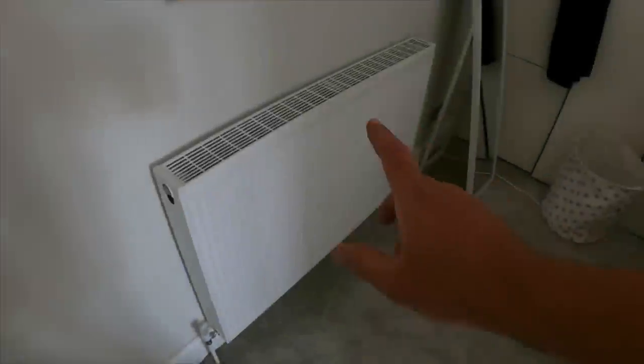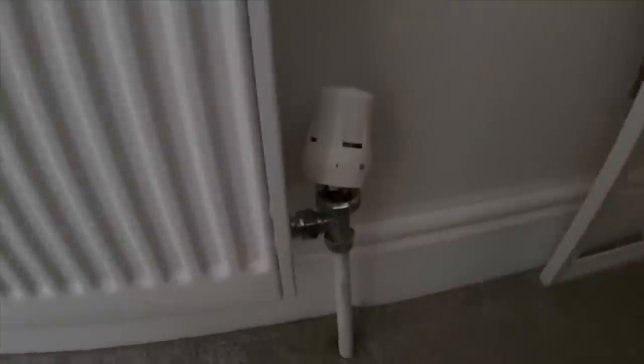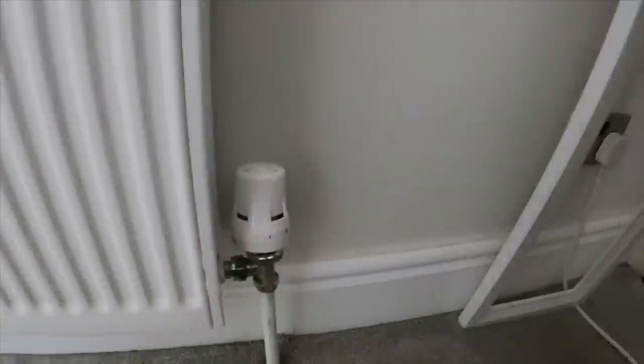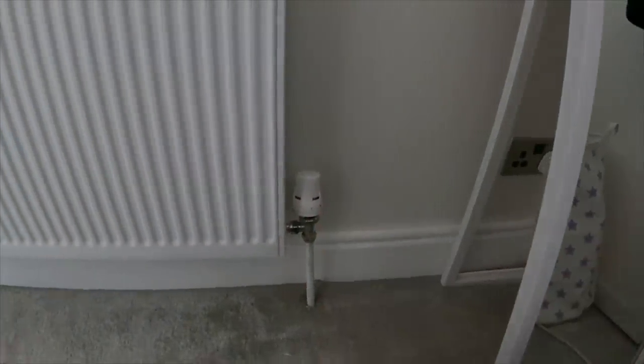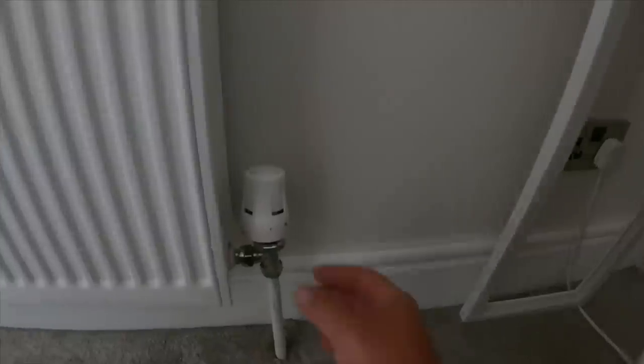Next, a couple of radiators on the first and second floor — the heads are broken so they can't control the heat on or off. We've gone upstairs to have a look. This is the radiator on the first floor front lounge and as you can see the thermostat head is snapped off — that's why they can't control it. We'll whip that one off, replace it. There's one above as well — probably the same predicament. I think it's a Danfoss one so we'll go match it up.